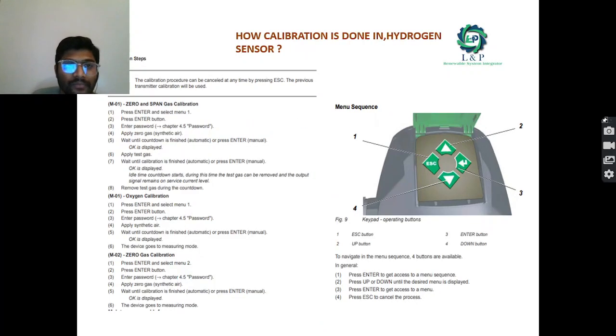Next, the first most important thing is how the calibration is done. If you want to do the calibration process, first, using the enter button inside the sensor, go inside M01. Once M01 is selected, you need to enter the password. There is a default password, which will be four zeros. If you want, you can change it with the advanced settings options, but the default will be zeros. And you need to apply the zero gas.